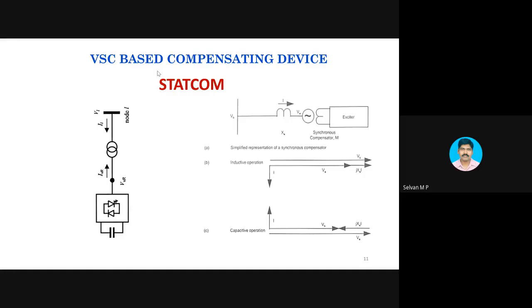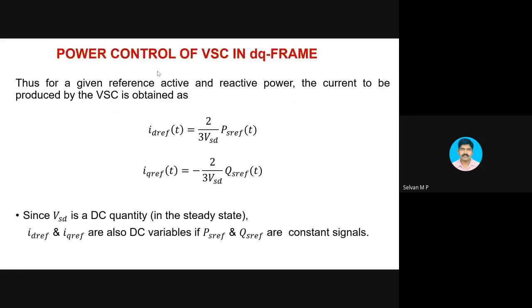Armature control and field control. DC machine you might have studied. Field control will not affect armature operation. Armature control will not affect the operation of the field. In that way, we can bring a control in this. I'm not going in depth on these mathematical equations, which several professors might have covered for you. So ID and IQ. IQ can be written in terms of Q, reactive power, and ID can be written in terms of real power. So if I want to control real power, I have to control ID. If I want to control reactive power, I have to control IQ. Is that the convention?